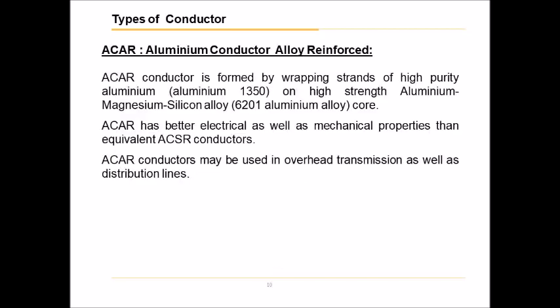ACAR — aluminium conductor alloy reinforced. ACAR conductor is formed by wrapping strands of high-purity aluminium on a high-strength aluminium-magnesium-silicon alloy core. ACAR has better electrical as well as mechanical properties than equivalent ACSR conductors. ACAR conductors may be used in overhead transmission as well as distribution lines.